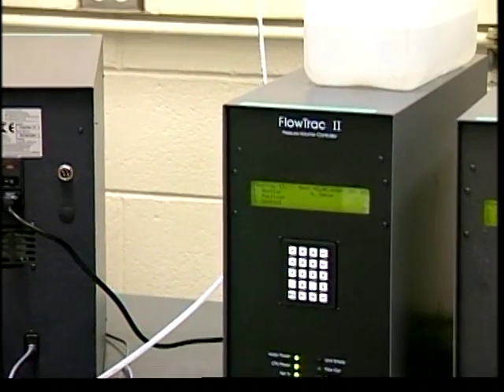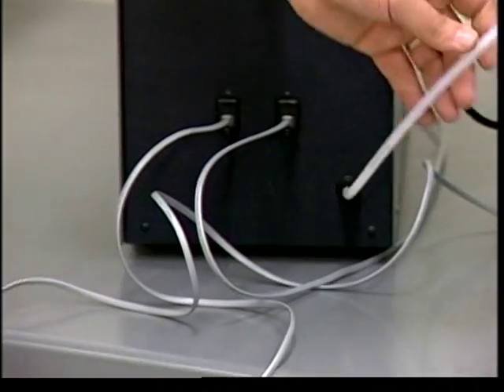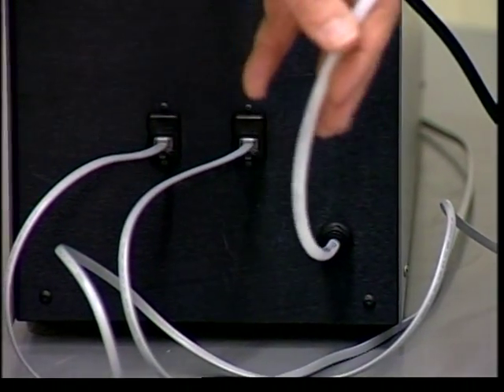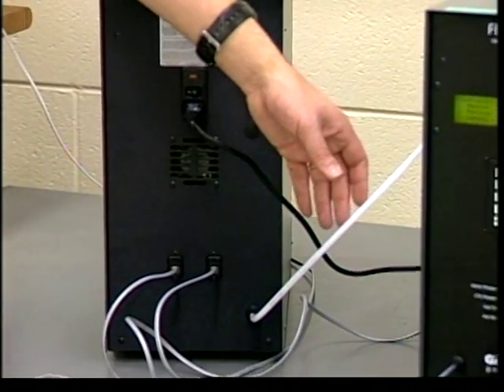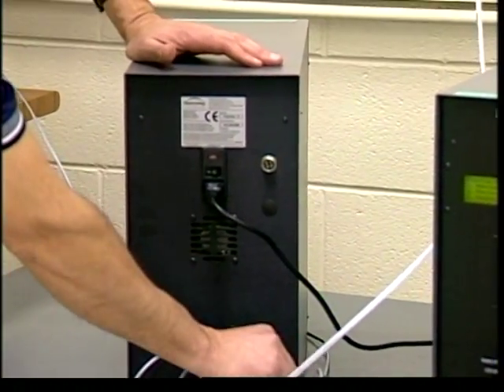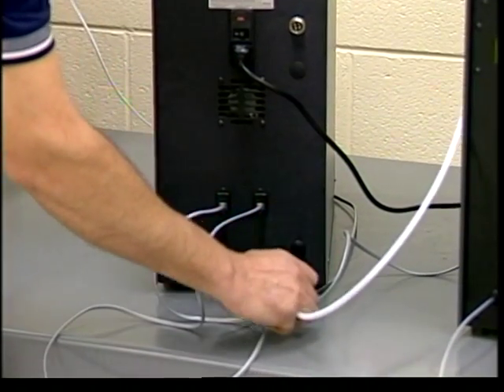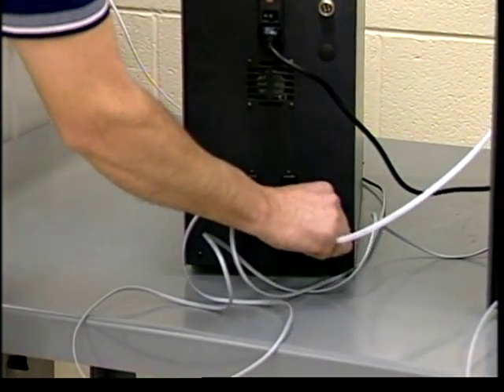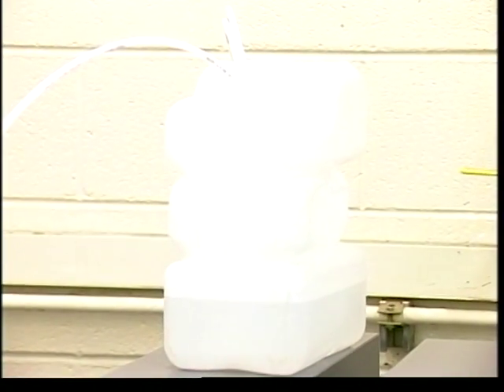The water supply is connected to the back with this 1/4 inch tubing. That's about 6.3 millimeter. The tubing comes here, and all you do is push it in until it clicks. If you want to take it out, you have to push the ring back and push the tubing out. This is a connection in the back, and you dip this into the water. Make sure you always have water, preferably, and what I recommend is to have de-aired water. Very important for some of the tests that you're going to be running.